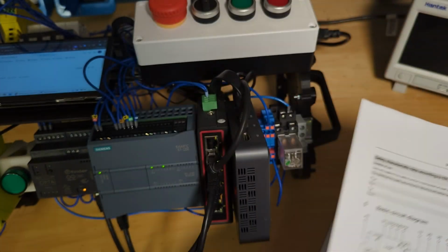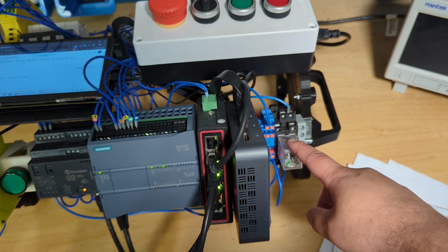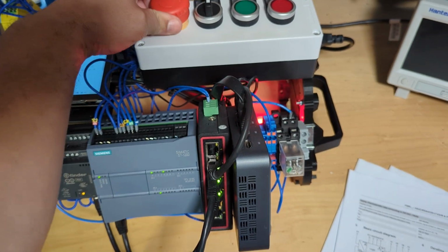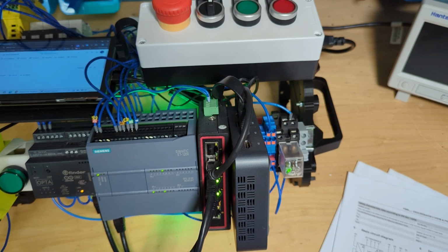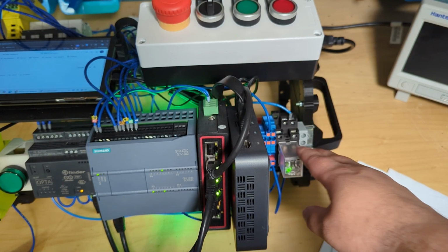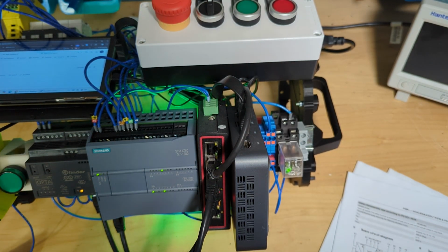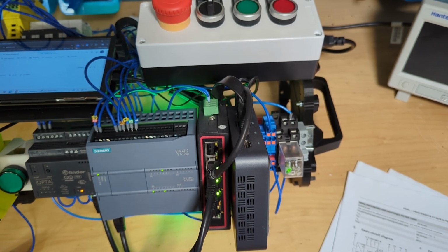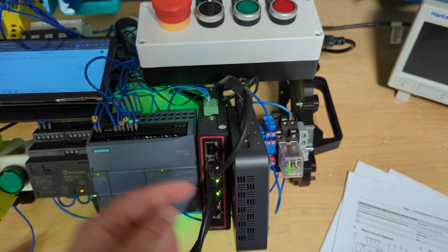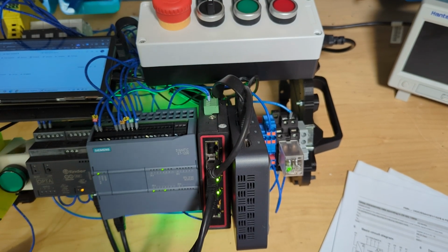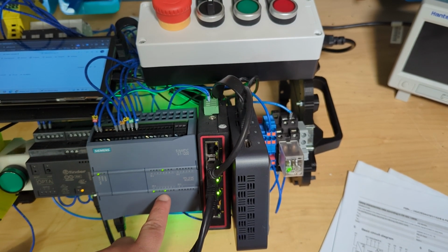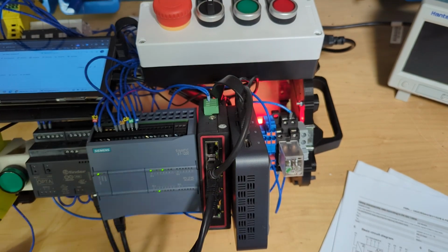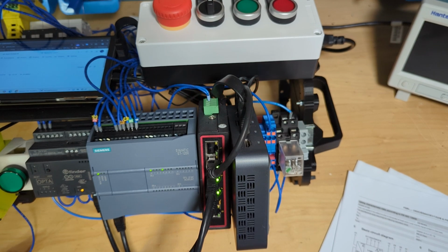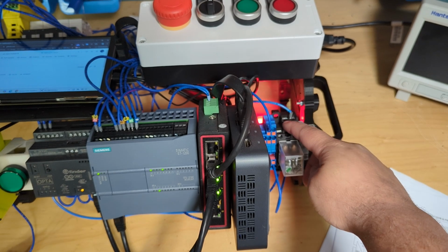And what that means is that whenever the e-stop is unhappy, until I reset it, this relay has no power and it has no ability to drive anything. But once I reset the e-stop, it allows the relay to fire again. So right now I've got my output on my PLC on. If I hit the e-stop, that kills my output there, because my PLC detected that I don't have the e-stop. But on top of that, I just have no power here anyway.